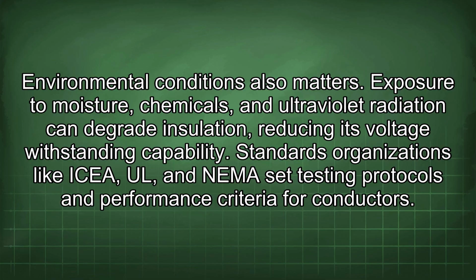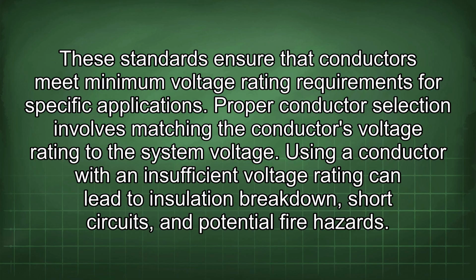Standards organizations like ICEA, UL, and NEMA set testing protocols and performance criteria for conductors. These standards ensure that conductors meet minimum voltage rating requirements for specific applications. Proper conductor selection involves matching the conductor's voltage rating to the system voltage. Using a conductor with an insufficient voltage rating can lead to insulation breakdown, short circuits, and potential fire hazards.